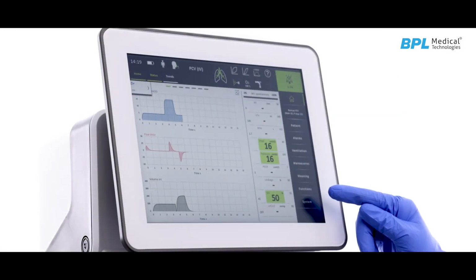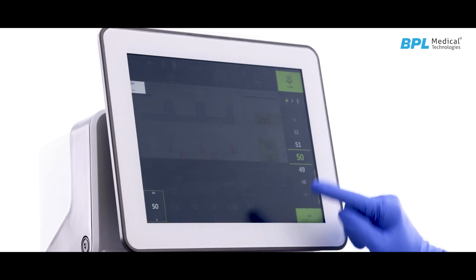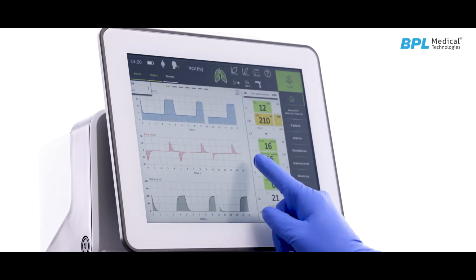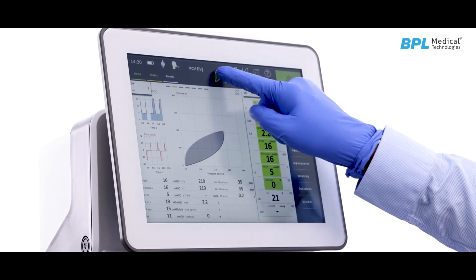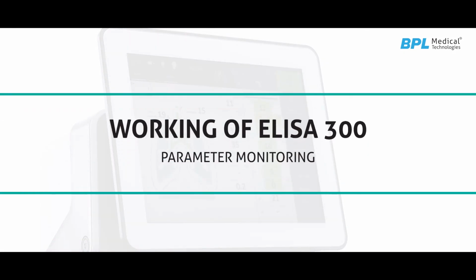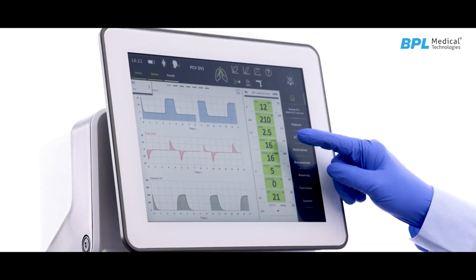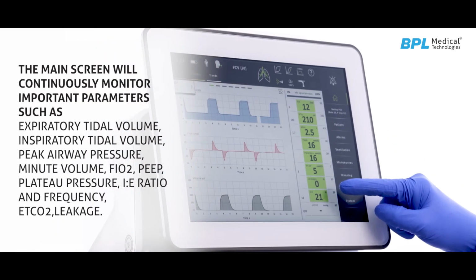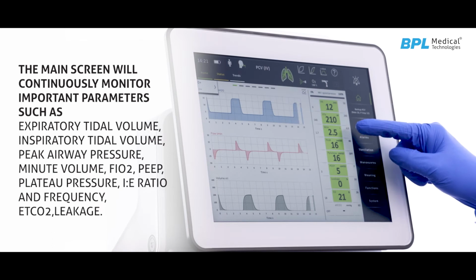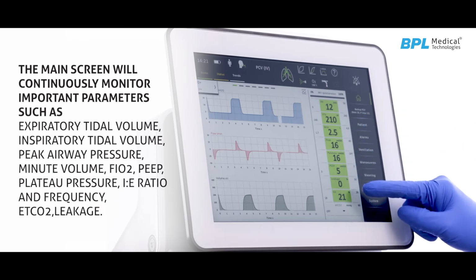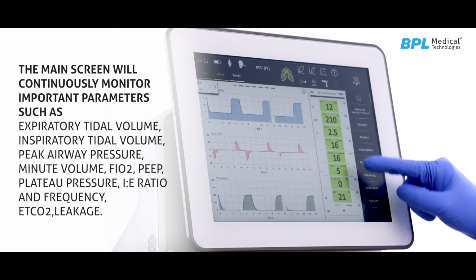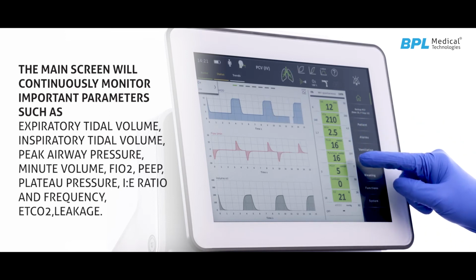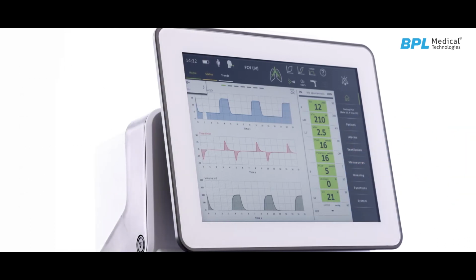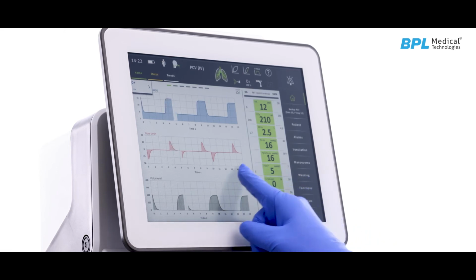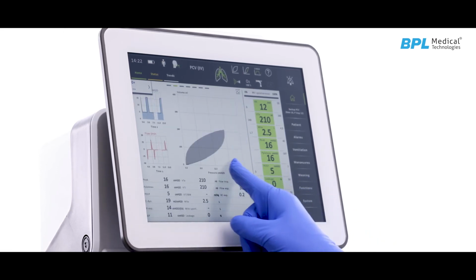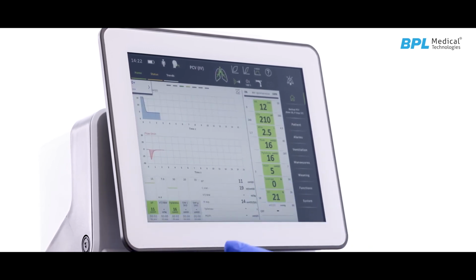The screen is mainly divided into 5 zones: ventilator control, monitoring of patient numeric parameters, waveforms and loops, alarm message area, and shortcuts and dynamic lung contour. The main screen will continuously monitor important parameters such as expiratory tidal volume, inspiratory tidal volume, peak airway pressure, minute volume, FiO2, PEEP, plateau pressure, I/E ratio and frequency, EtCO2, leakage. More parameters like loops, weaning protocols, work of breath data with adaptive graph, resistance, compliance, and inspiratory-expiratory flow can be seen by swiping the screen.